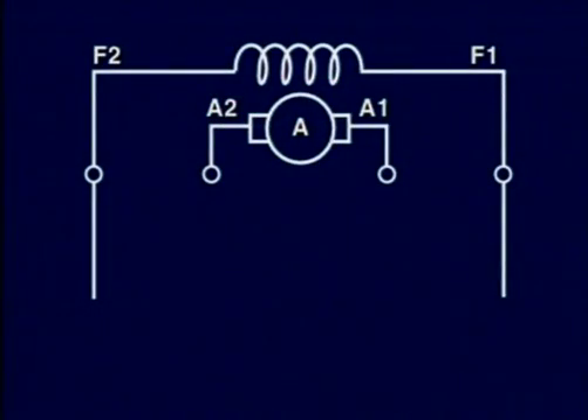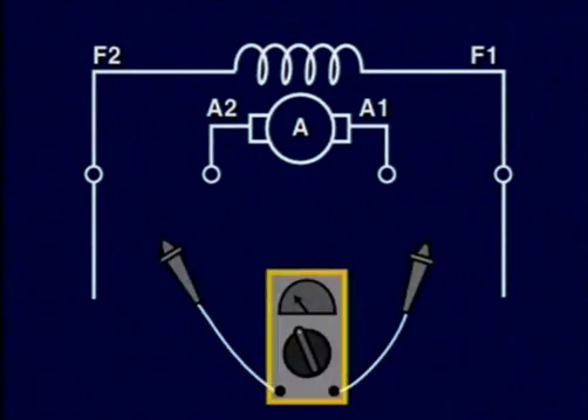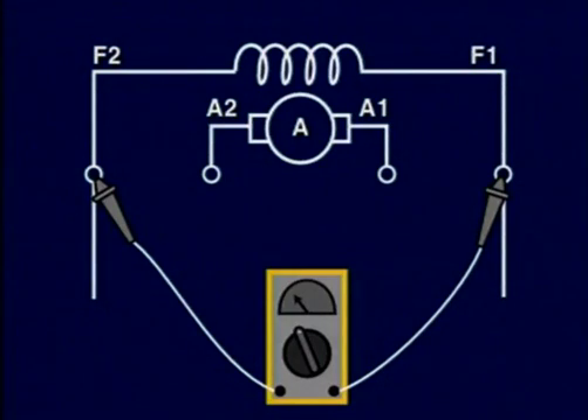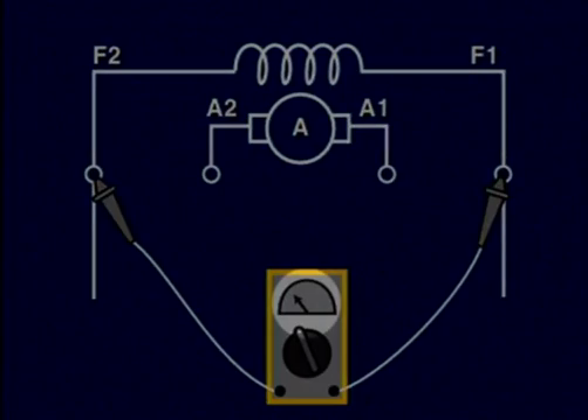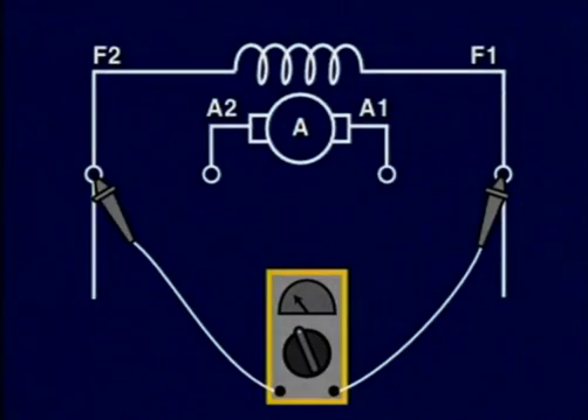To test the field winding for an open, we use a procedure similar to the one used with a series motor. With the meter set for ohms, we place the two terminals across the F1 and F2. Make sure that the ohm meter is set to a resistance setting of R times 10K ohms, because the resistance of the field winding in a shunt motor is high, due to its winding being formed by a very long wire. If the reading from the meter shows resistance, then the field winding is good and has continuity. If the reading shows infinity resistance, then the field winding has an opening, and the motor must be repaired or replaced.